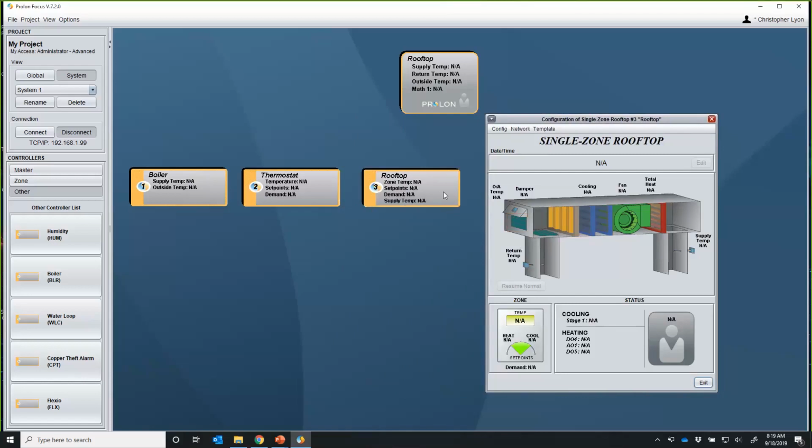Remember, this is a slave device, so it does not have the ability to talk to a C1000 if it wanted to. Because of that whole master-slave relationship, two slaves can't chat with each other. A slave can only talk to a master. That's why we had to use the RTU version. I'll show you that in just a sec. But now down here, config dehumidification.